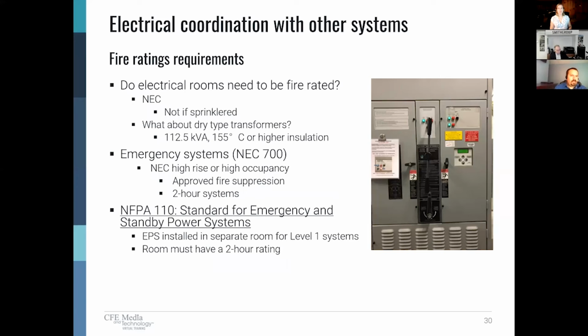So as we get into the electrical rooms, there are specific instances where we need to rate the room, and not all electrical rooms need to be rated. Brian touched on this earlier. The NEC specifically requires that if we don't have a sprinklered building, the room have a fire rating. I think Brian mentioned that was a 2-hour rating. And then we've got electrical rooms that have dry type transformers in excess of 112.5 kVA. If they do not have 155 degree C or higher insulation, they must also be rated. So those are two examples.